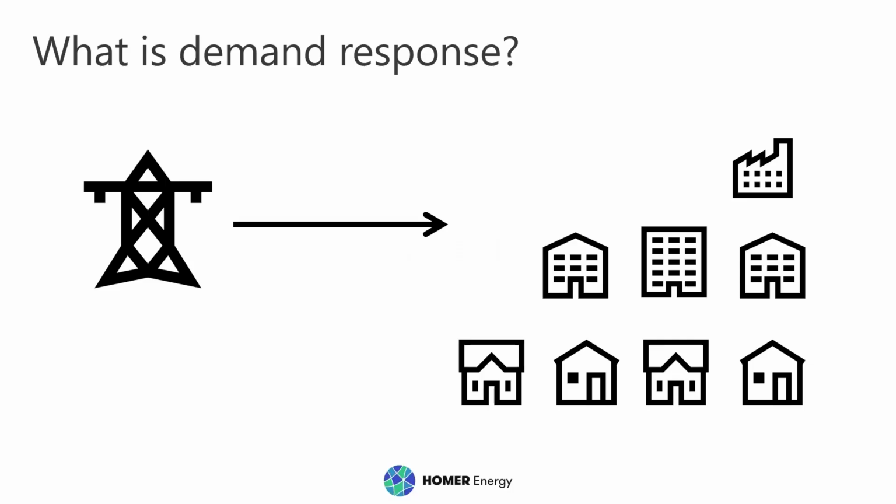Demand response programs are offered by the utility, and when the system demand peaks close to the generation capacity, the grid may become unstable with blackouts and brownouts. Generally, this could be on weekday afternoons of summer months because of the air conditioning load. As a way for utilities to avoid adding additional peaking generators, which are very expensive because they sit idle for most of the time, except for those 1 or 2 times per year when they need to jump on, the utilities are choosing to set up demand response programs which call on their customers to reduce their electrical demand during certain dates and times.